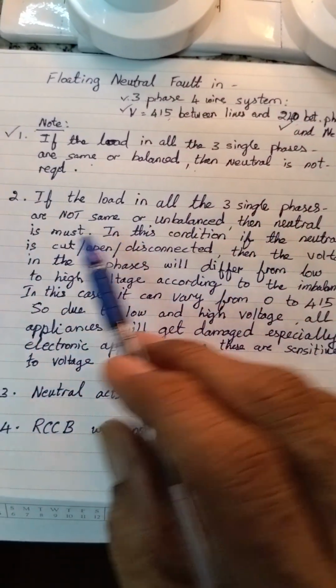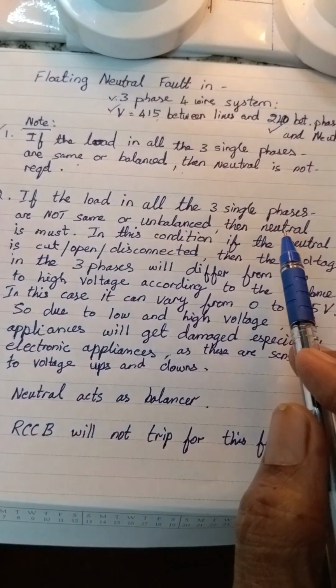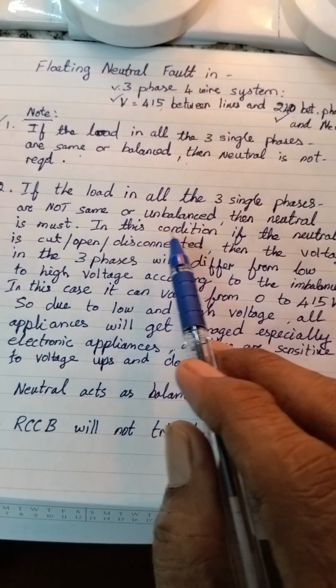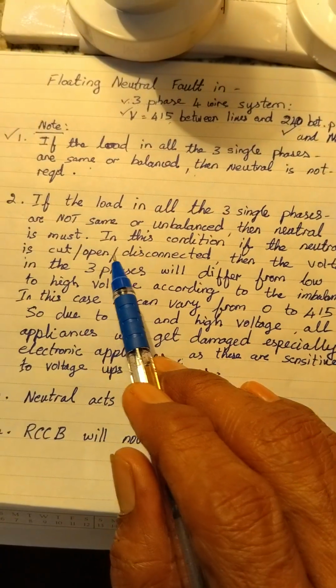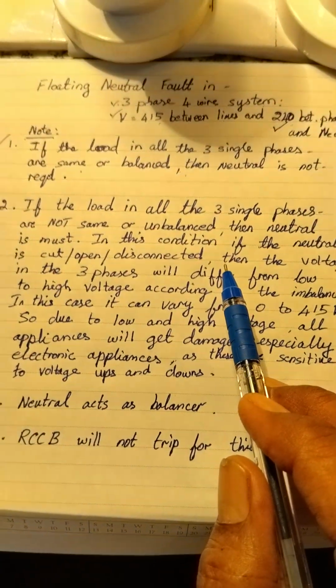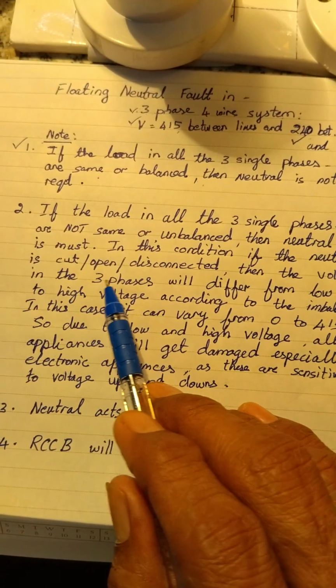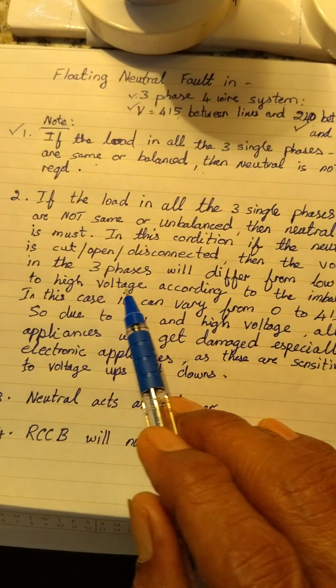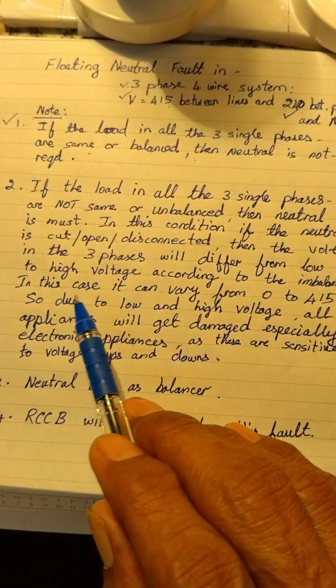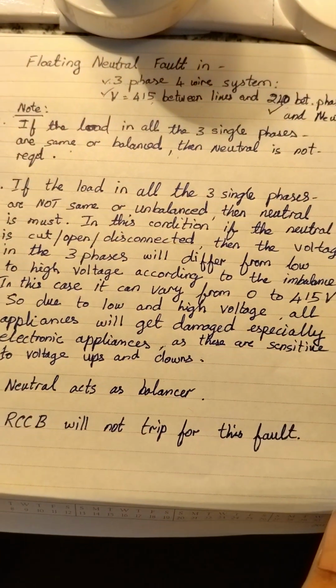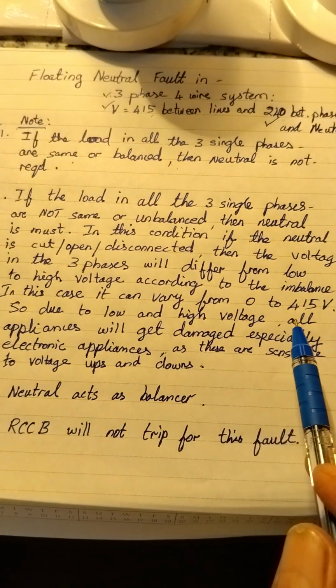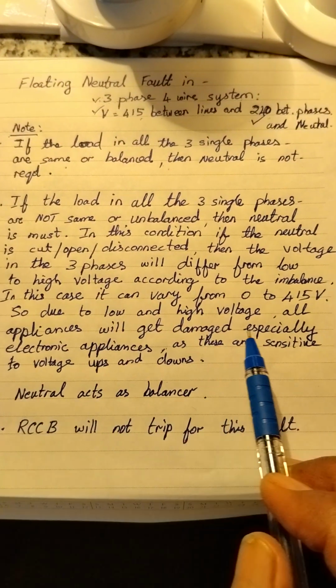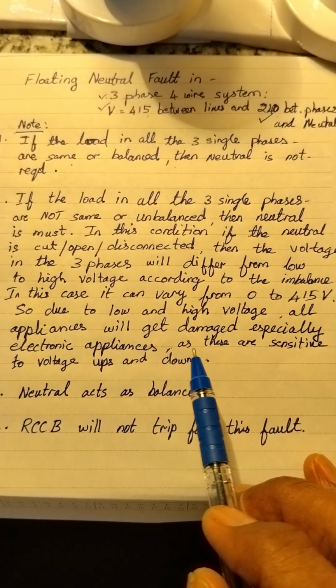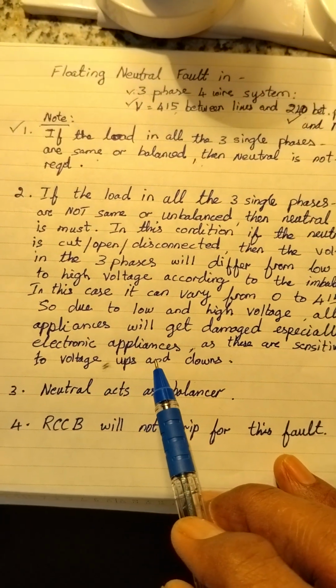Now we will go to the second note. If the load in all the three phases are not same or unbalanced, then neutral is a must. In this condition, if the neutral is cut, open, disconnected or loose, then the voltage in the three phases will differ from low to high voltage according to the imbalance. In this case, it can vary from 0 to 415 volt. So due to low and high voltage, all appliances connected to the circuit will get damaged, especially electronic appliances, as these are sensitive to voltage ups and downs.